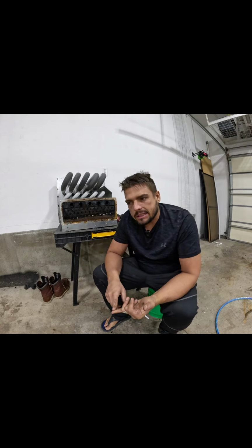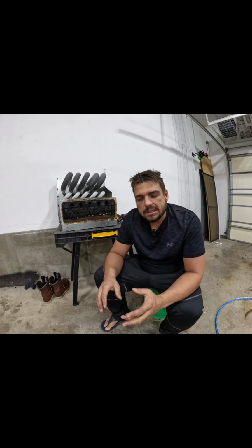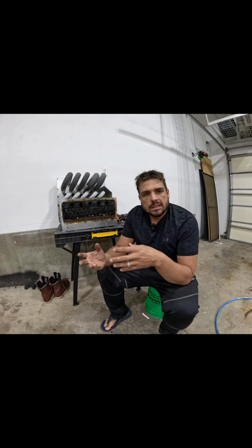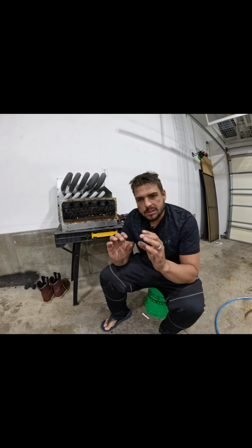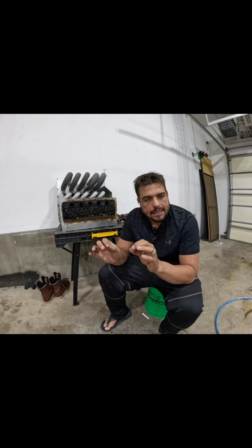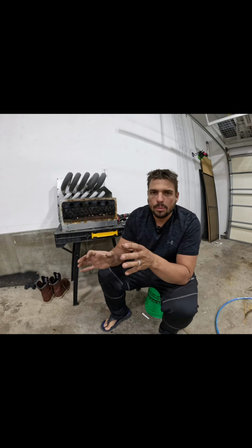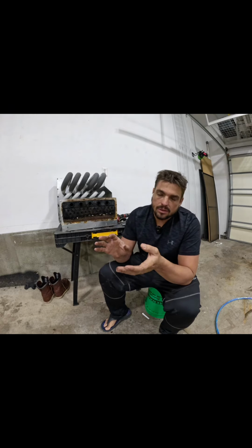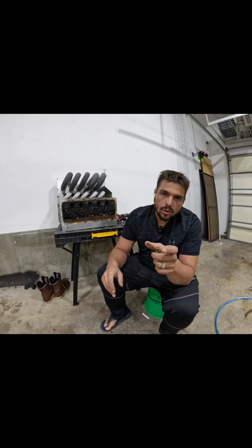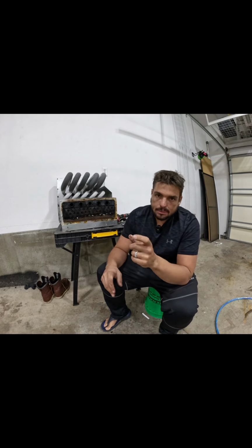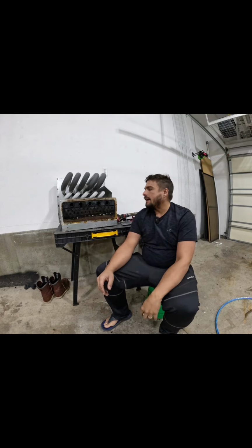Either the unit wasn't properly installed in the first place. When you install a furnace, there's a gas valve, and you're supposed to alter the gas pressures so it's burning appropriately. Inside the furnace it'll show manifold pressure, and you're supposed to match your furnace up with that.